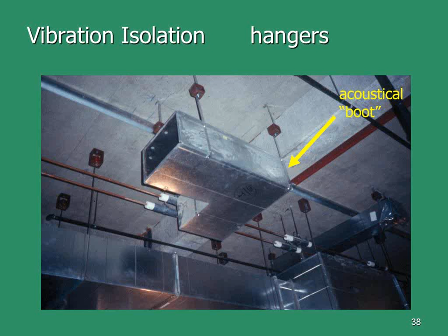So we already talked about the fact that rubber pads don't work for very low frequency stuff. There's a picture of an acoustical boot. Now in this case, there's absolutely no reason whatsoever for that to be on isolation hangers. There is for this big duct, but there's no reason for the boot to be. But I think there was just this blanket spec: every piece of ductwork must be on isolation hangers. There's not a lot of rumble occurring in this, and there's ultimately going to be a wall built across here. So this is what an acoustical boot really looks like in the field, and it's more than just the elbow.